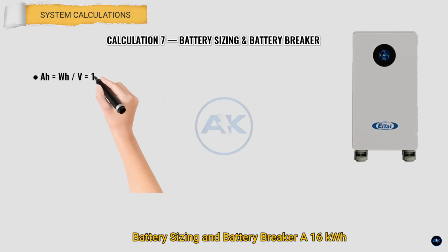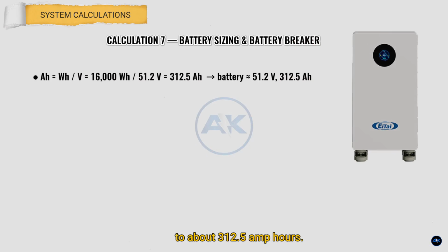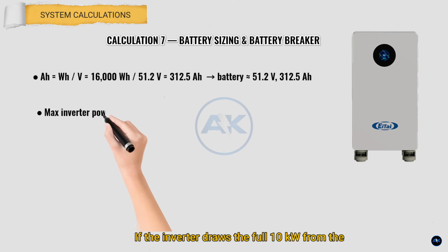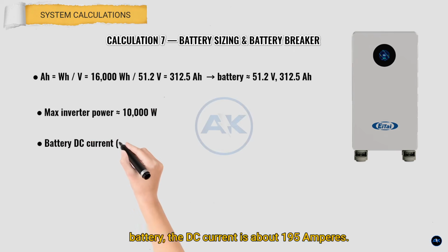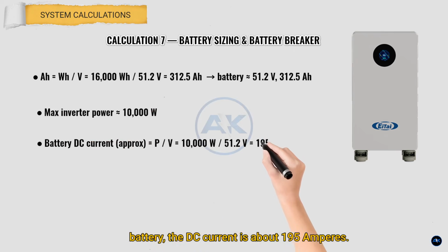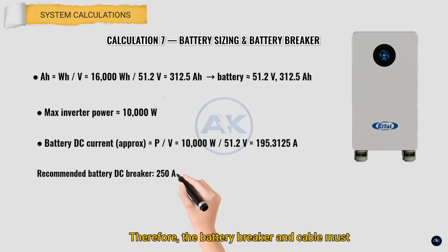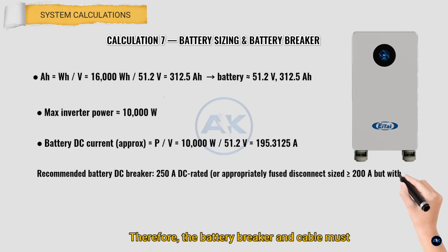Battery sizing and battery breaker. A 16 kilowatt-hour battery at 51.2 volts corresponds to about 312.5 amp-hours. If the inverter draws the full 10 kilowatts from the battery, the DC current is about 195 amperes. Therefore, the battery breaker and cable must safely carry that current.